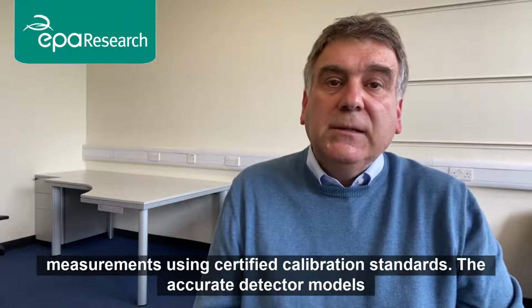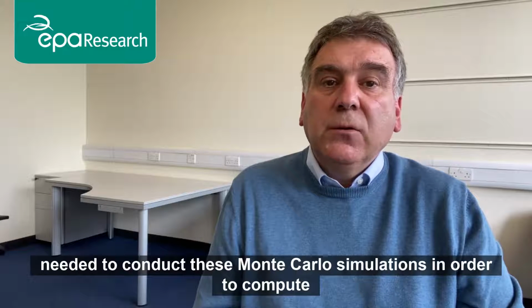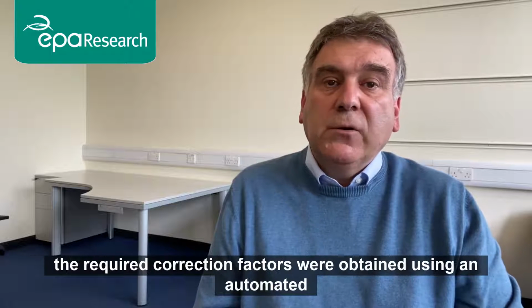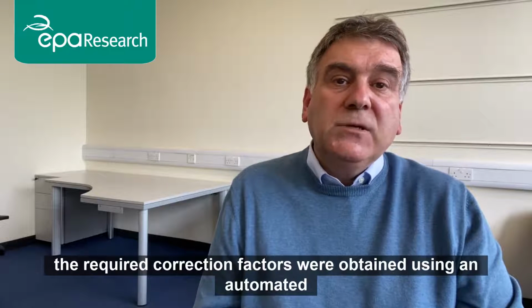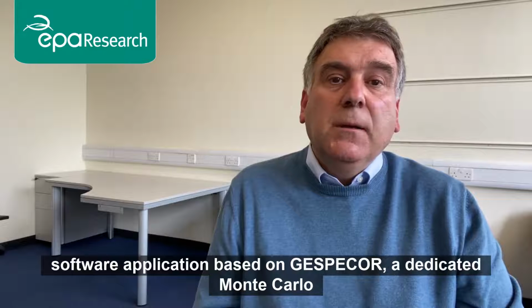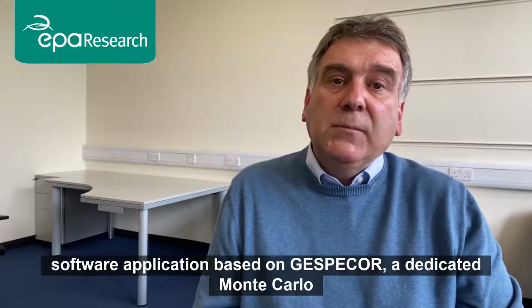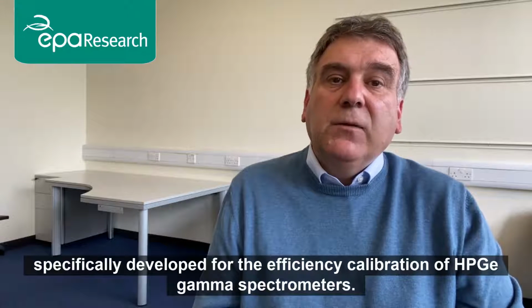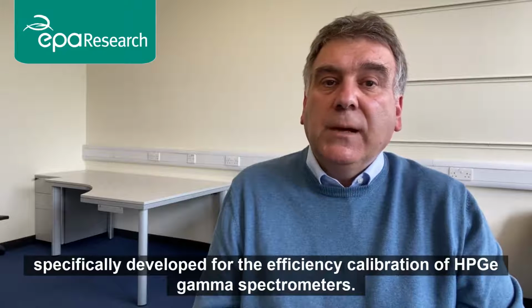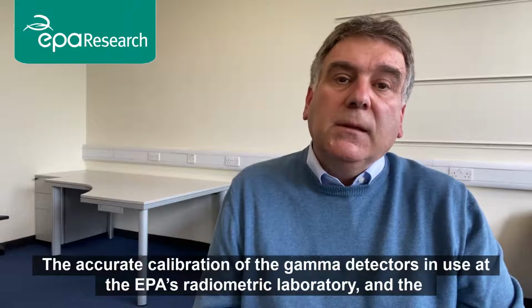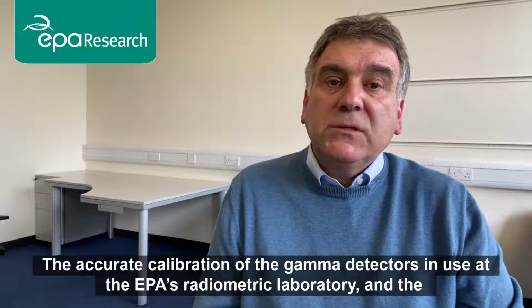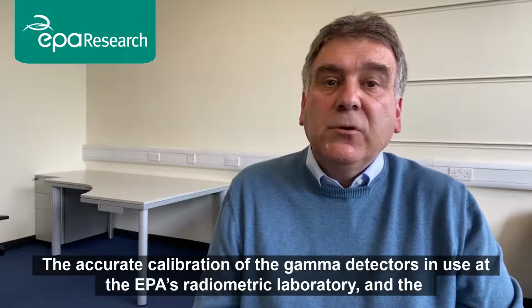The accurate detector models needed to conduct these Monte Carlo simulations, in order to compute the required correction factors, were obtained using an automated software application based on GESPECOR, a dedicated Monte Carlo package specifically developed for the efficiency calibration of germanium gamma spectrometers.